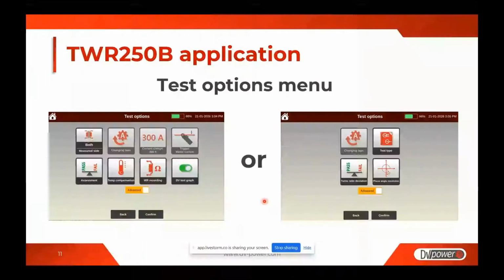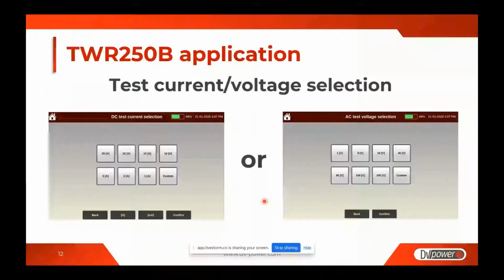When you press the test current and voltage selection, depending on the selected test, you will be able to select the DC test current for winding resistance measurement, and the selected value can be in amps or milliamps, or the value can be customized. Maximum value is 25 amps. For turn ratio test, you can select a value of 1 volt, or at maximum level 250 volts.